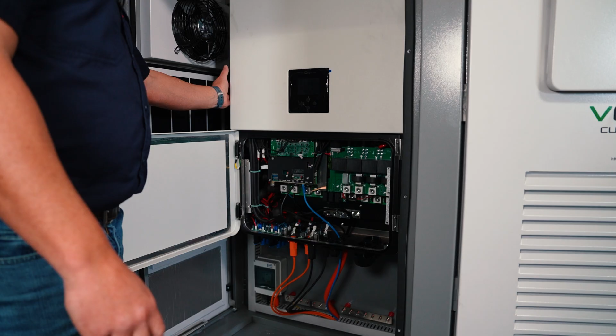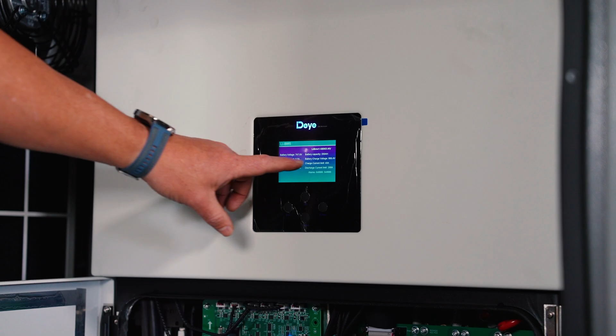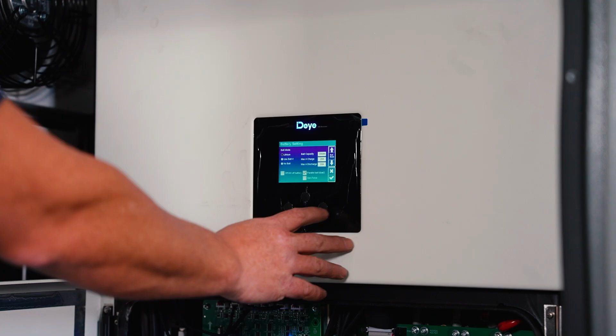Okay guys, so if you do want to see if your battery does have communication with your inverter, go to your battery icon, press on it, go to the bottom right hand corner, LIBMS, then you will see all your values over here. The main things to look at are your battery voltages, your battery temperature, state of health, your charge and your discharge current. You'll see at the top here it will flicker between Pylon and Volta batteries. That means you've got communication. When you receive the units from us, your battery settings have already been done for you. The only things that you still have to do on site are system work mode, generator settings, and your time of use.